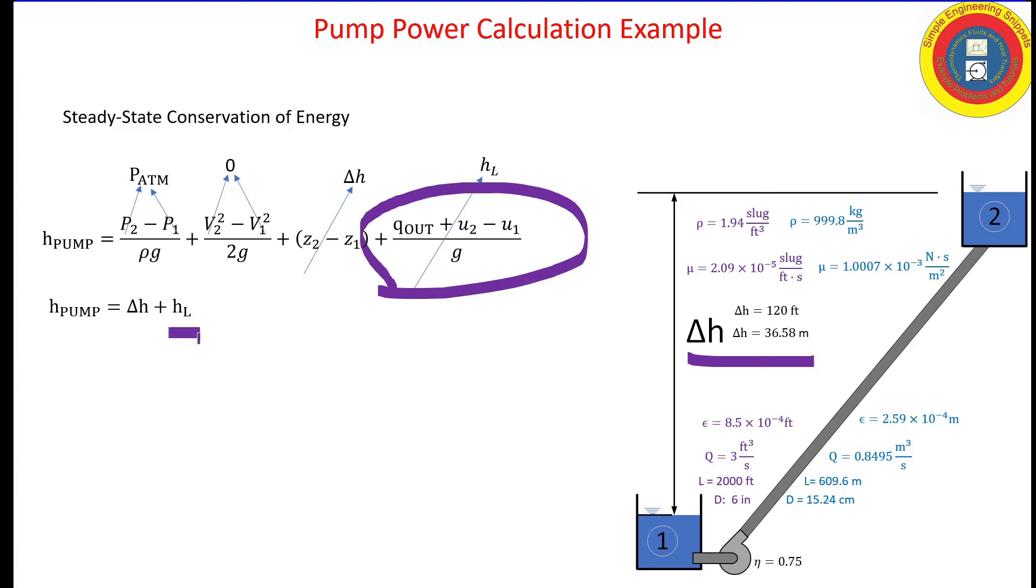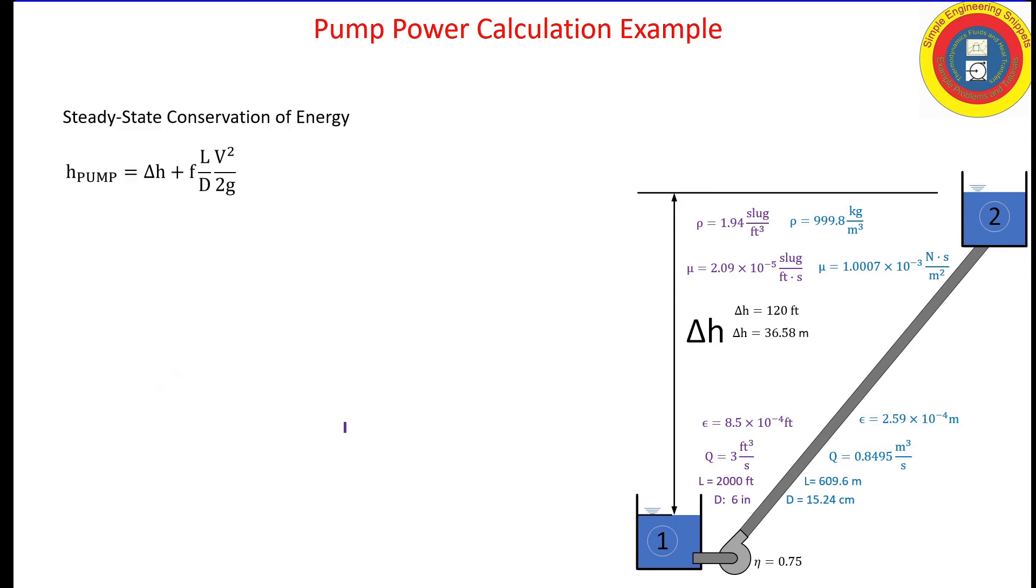What is head loss? We'll use the Darcy-Weisbach equation for head loss. The friction factor times length over diameter times velocity squared over 2g. We know the flow rate. We know the diameter. So all the terms are readily known except for the friction factor.